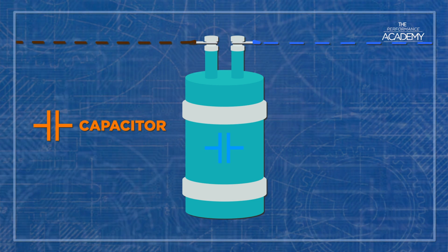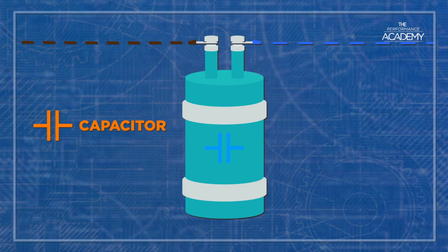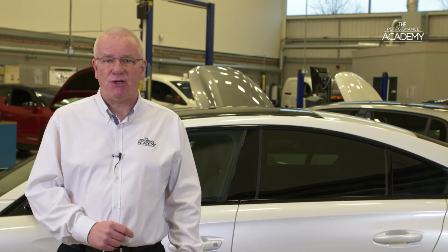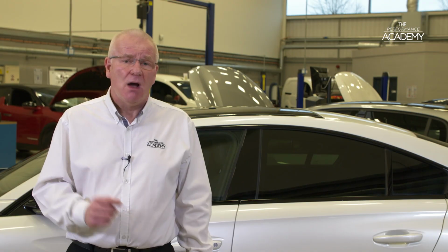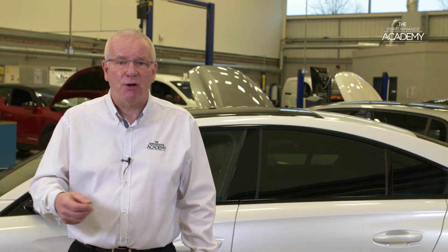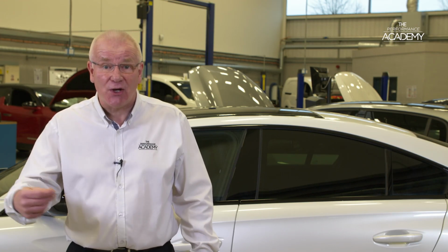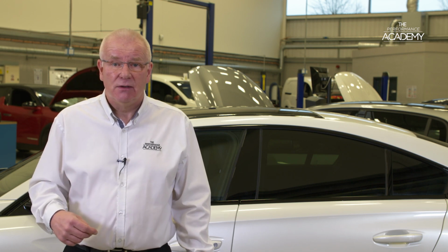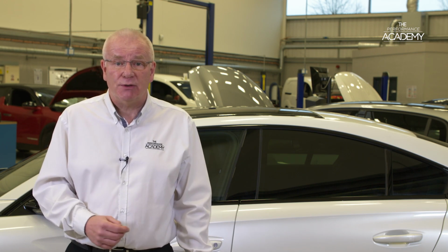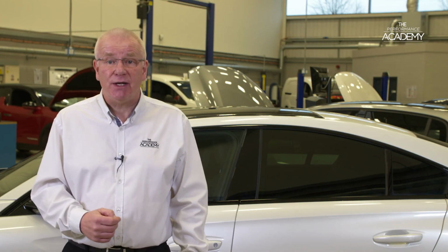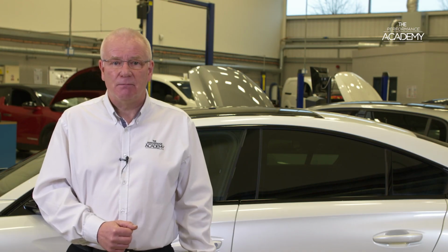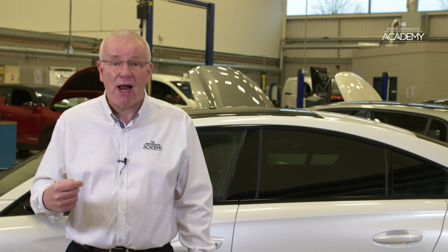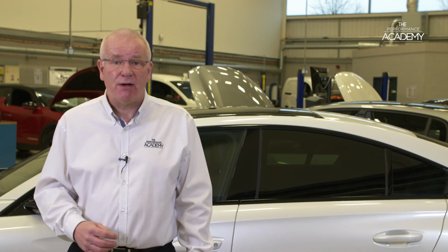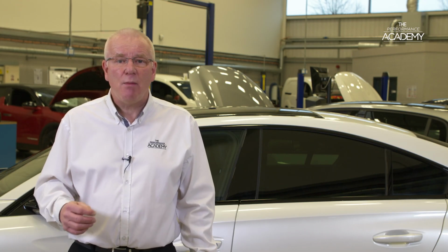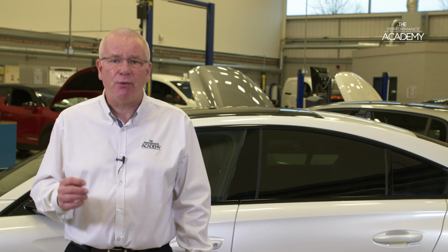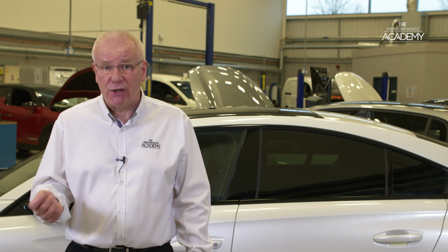Furthermore, the tests we are instructed to carry out are in many cases an imperfect resistance test. Remember, correct test procedure requires the complete isolation of the circuit to be tested and no other voltage to be present. High capacitance in components, as we mentioned earlier, creates an opposing voltage, and we may not be properly able to isolate the circuit we are testing. Not ideal conditions then. But rather than have to disconnect everything in the vehicle or the components you are testing, PSA engineers have pre-tested good circuits to take into account these less than ideal test conditions. All these variables together can produce the fluctuating value you're trying to read on the tester. This is also why the recommended test duration is always more than 10 seconds, with a 1-minute test recommended for larger circuits to put the insulation under pressure and to properly assess the minimum megaohm reading being shown.